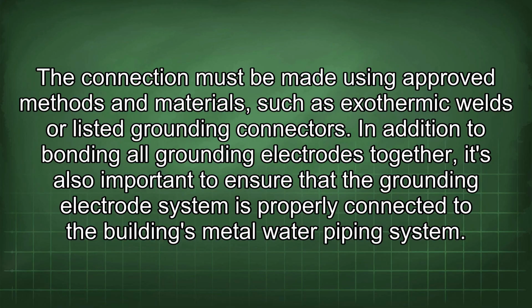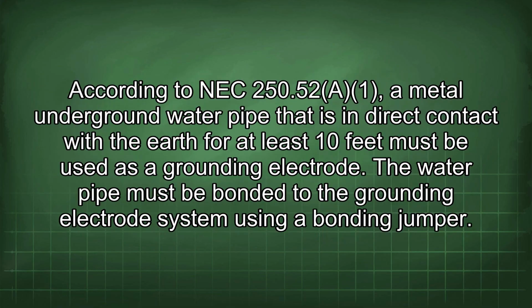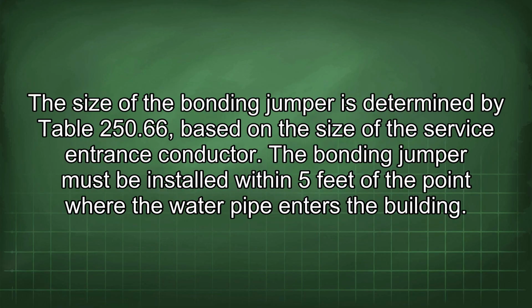In addition to bonding all grounding electrodes together, it's also important to ensure that the grounding electrode system is properly connected to the building's metal water piping system. According to NEC 250.52(A), a metal underground water pipe that is in direct contact with the earth for at least 10 feet must be used as a grounding electrode. The water pipe must be bonded to the grounding electrode system using a bonding jumper. The size of the bonding jumper is determined by Table 250.66 based on the size of the service entrance conductor.